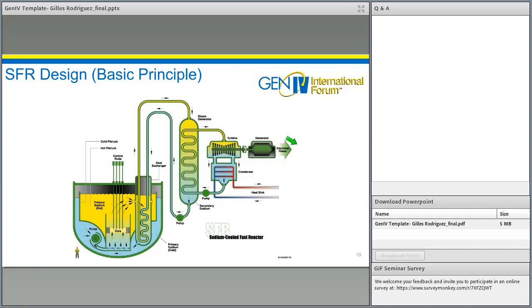in order to produce electricity. And so in that case, as I was telling you, the major drawback of sodium, its chemical reactivity, forces us to provide an additional circuit, which you can see here, to produce steam through the steam generator with a pump. So we cannot directly add the steam generator inside the primary vessel because of the bad consequences that we could have from a sodium-water reaction in case of loss of tightness and the high depressurization of steam inside the primary vessel. So by using sodium, we were obliged to develop an additional circuit, what we call an intermediate circuit or sometimes a secondary circuit.